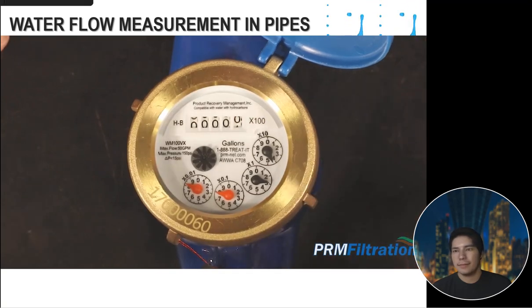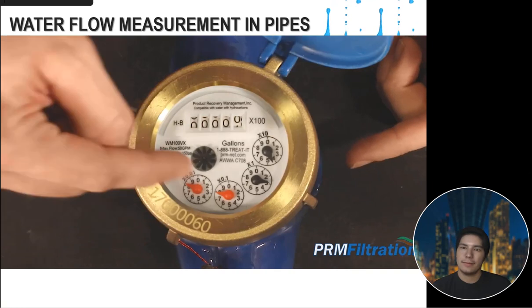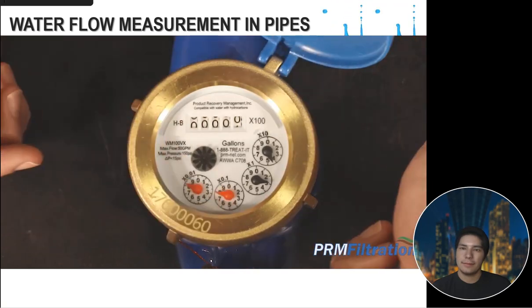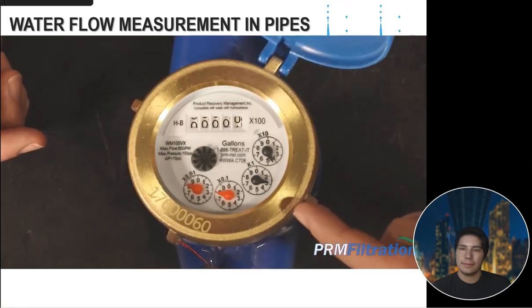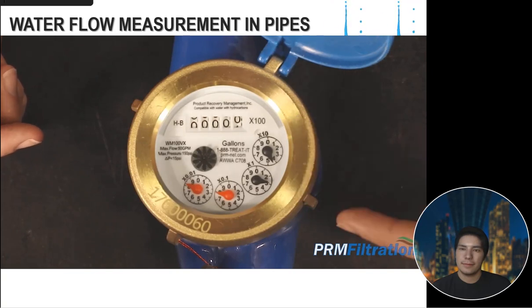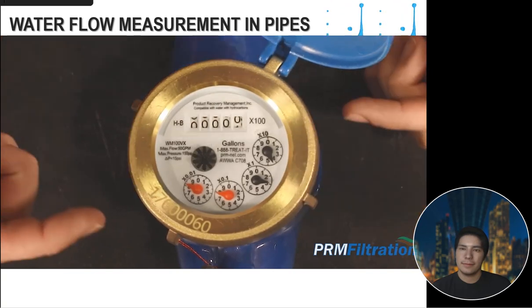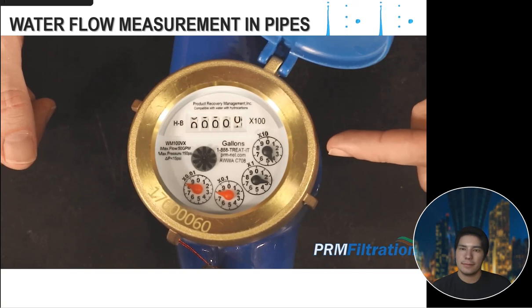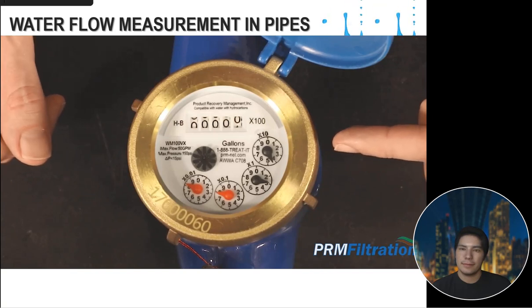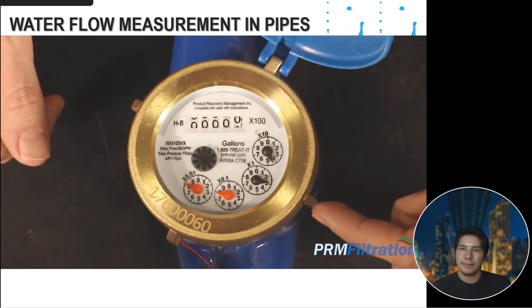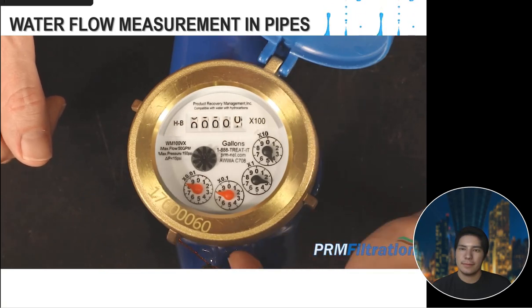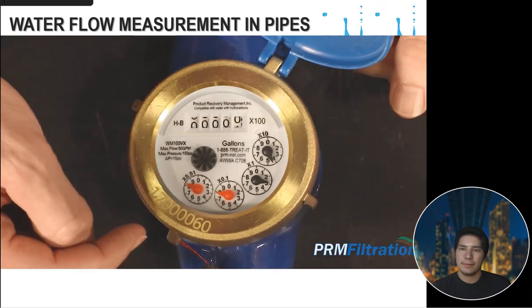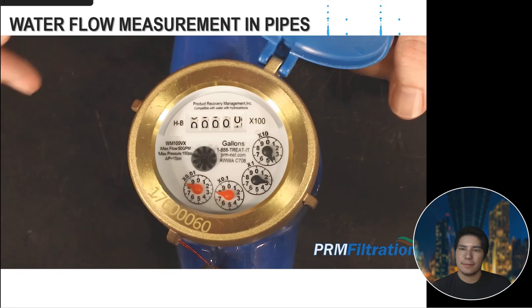As the water comes through this meter, it begins to spin these dials, and each dial will move the next dial up until it is moved to the counter. So this is 10 gallons. This is every 1 gallon. This is every 1/10 of a gallon. And this is every 100th of a gallon.